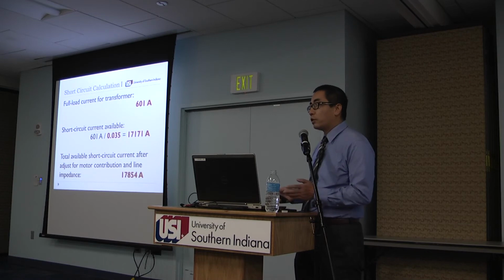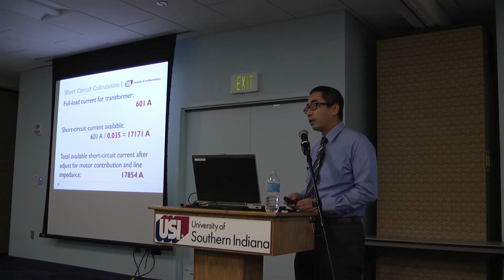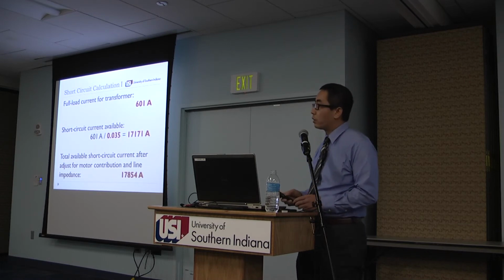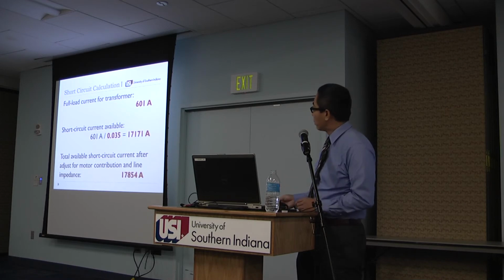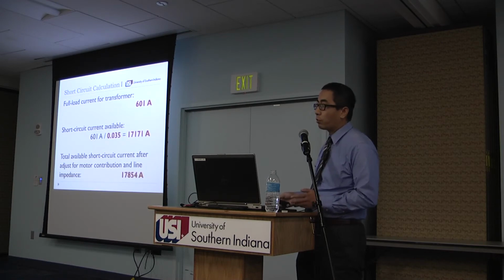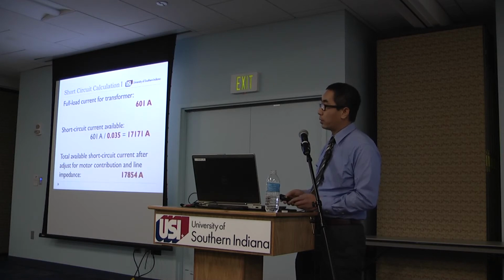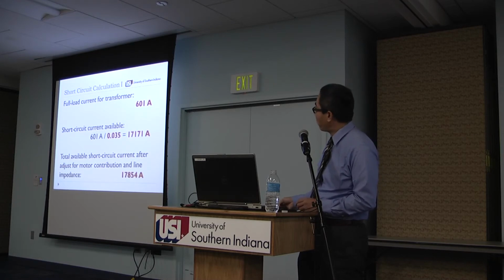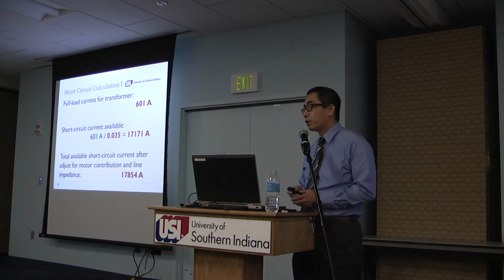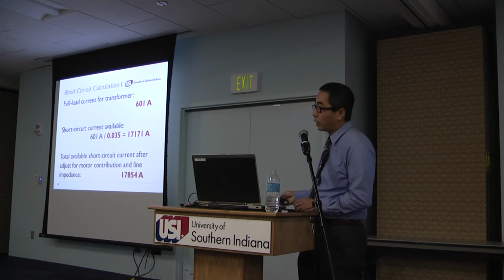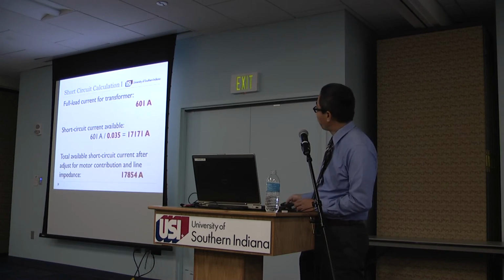And the fault can happen at the equipment, not at the transformer. So there's a wire running between them, and we need to deduct those losses at the wire. And also we need to consider that some of the motors may contribute additional current to the system. So after the adjustment, we got 17,854 amp. That's the short circuit current. When we pick the circuit breaker and fuse, we need to make sure they can withstand this short circuit current.